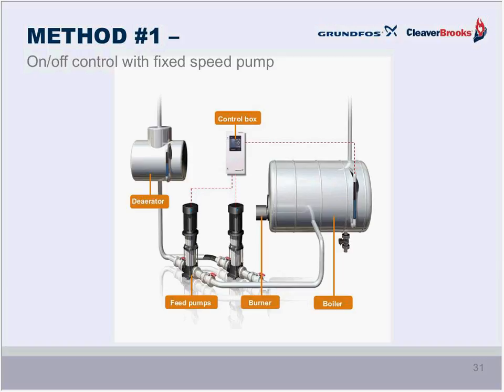I mentioned these are fixed speed, and they are intermittent duty pumps, so they will turn on and off. When the water level falls to that pump-on level, the pump starts moving a large quantity of relatively cool water into the boiler. When the pump-off level is reached, the sensor causes that pump to stop. Now notice, there's no bypass line going from the discharge of the pumps back to that deaerator tank. And there's also no feed valve between the pumps and the boiler.